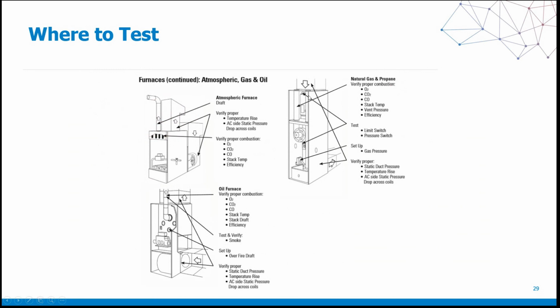Very important. And then we have your different systems here with your vent piping. Here's your places where you test in here. And then for the oil furnace, again, verify and test our oxygen, CO, and CO2 right up here in the actual termination piping. That's where we want to test for an oil system. And again, these are just general guidelines.